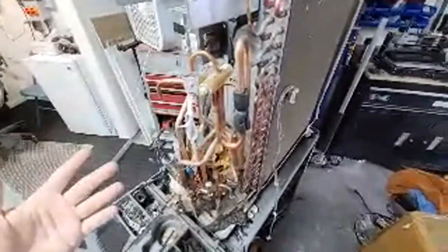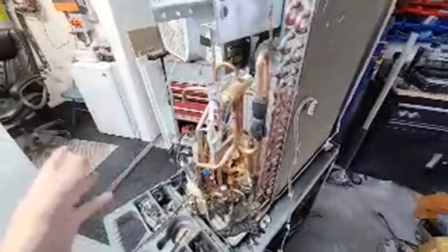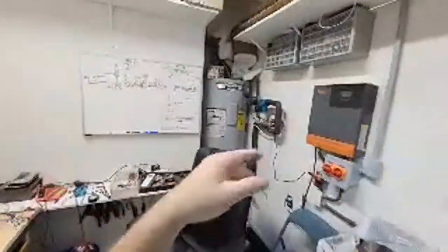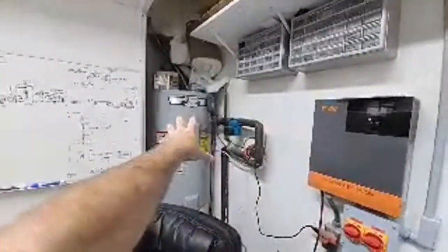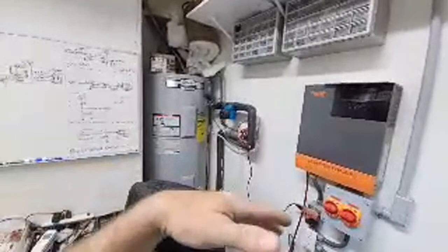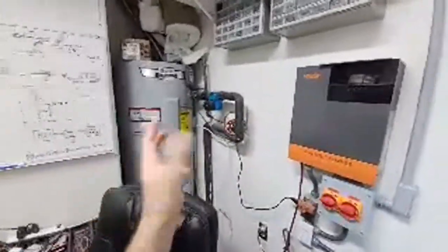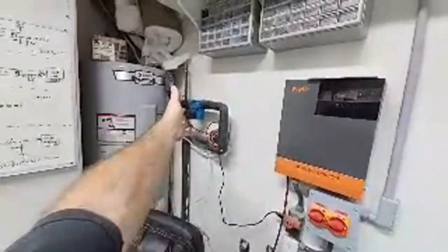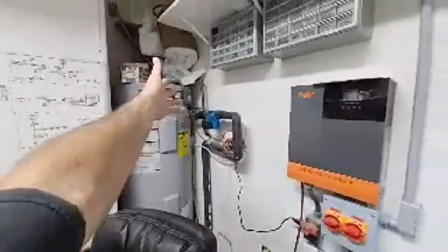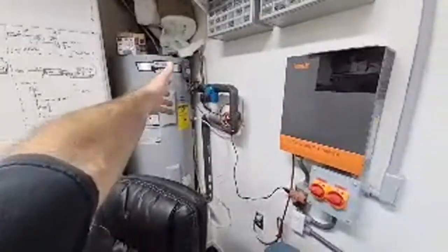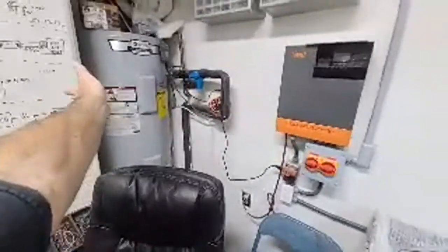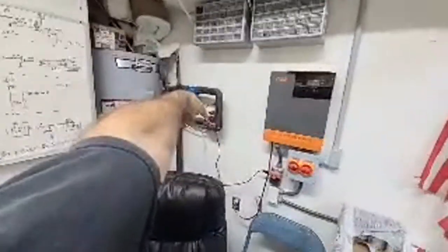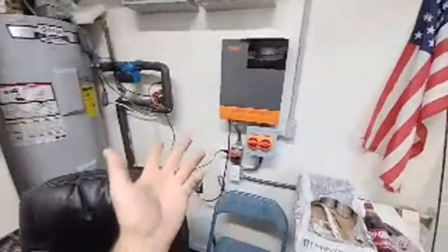And then, how should I say, at the times where I'm running it for cooling mode in the summer, and the water's already as hot as I can let it be, I'm going to put a safety switch in there. When it's below that high limit, it'll allow this pump to run when the unit's running, but when it hits like 140 or something, like a high limit, the water's really hot, I'll probably have it flip to where it just stops this pump and takes it out of the circuit.